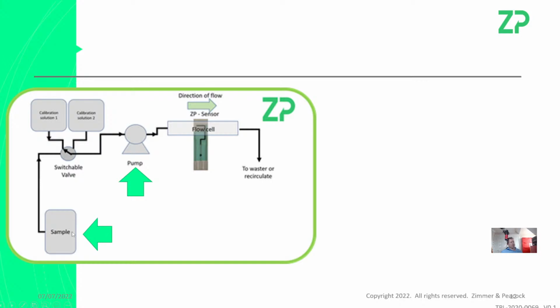So you have a sample or the reaction going on. You pull samples out of the reaction using something like a syringe pump, and you pump it over a flow cell here. We do have flow cells. If you Google Zimmer and Peacock flow cells, you'll start finding this kind of thing. And we have a switchable valve. Now the switchable valve allows you to pull from the sample or to pull from calibration solutions.